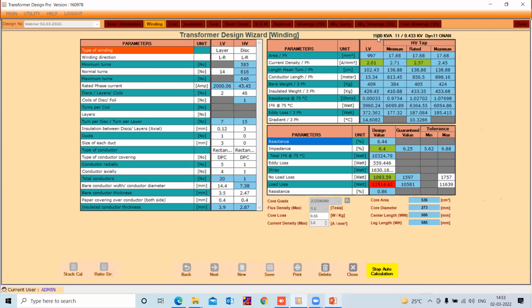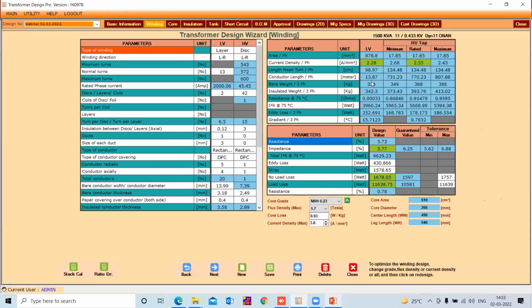Friends, we are on the winding card of the transformer. On the right hand side top, you can see 1500 kVA, 11 by 0.433 kV, that's the primary and the secondary winding. Dyn11 is the vector group, ONAN is the cooling. I draw your attention to the table just below, wherein the first column is the parameter, the second column is the unit, the third column is the LV winding, and the last 3 columns are the HV winding, with the minimum tap, the rated tap, and the maximum tap. Now let's go through the parameters one by one.